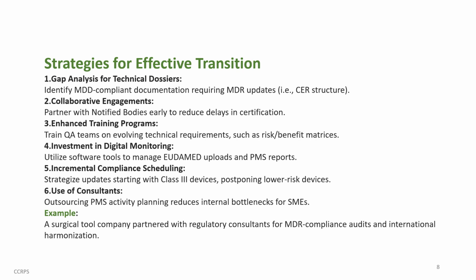Incremental compliance scheduling: strategize updates starting with Class 3 devices, postponing lower-risk devices. Use of consultants: outsourcing PMS activity planning reduces internal bottlenecks for SMEs. Example: a surgical tool company partnered with regulatory consultants for MDR compliance audits and international harmonization.